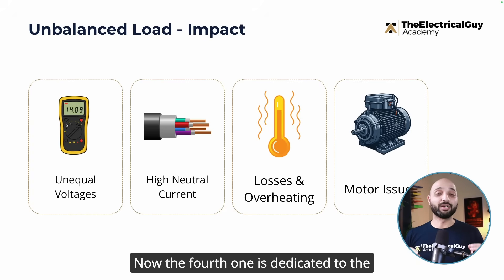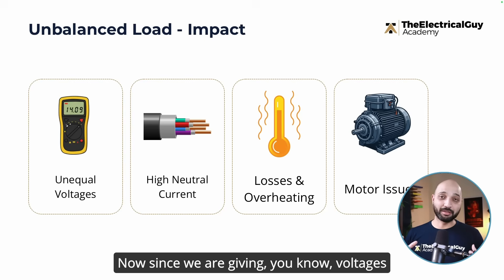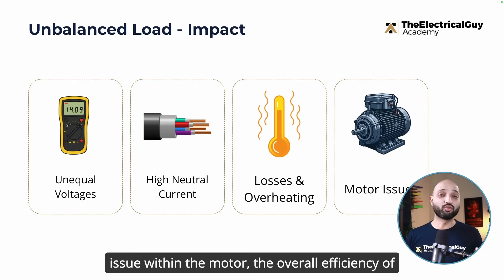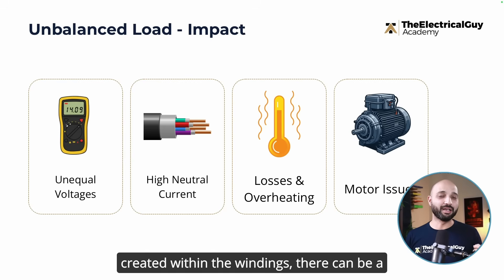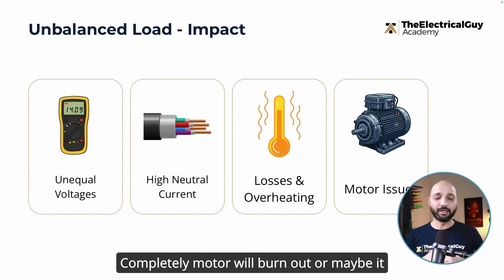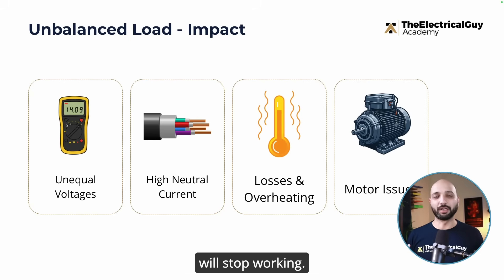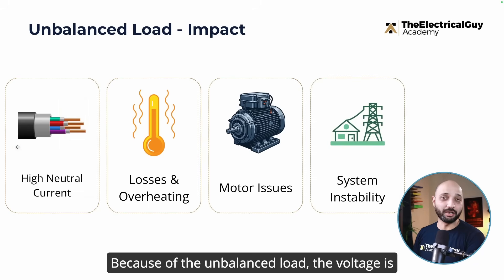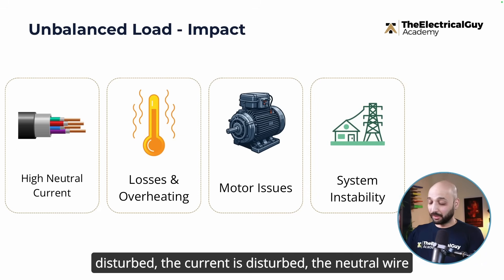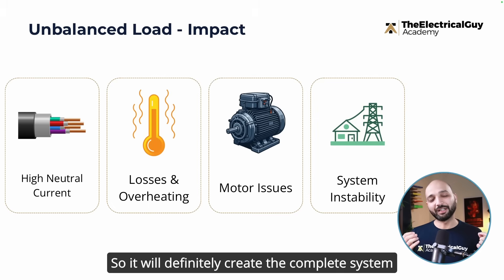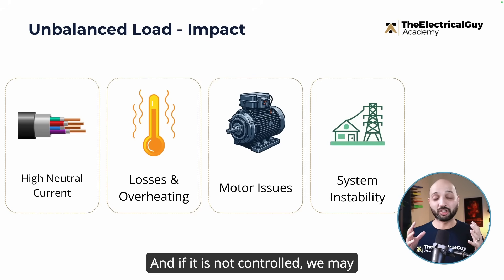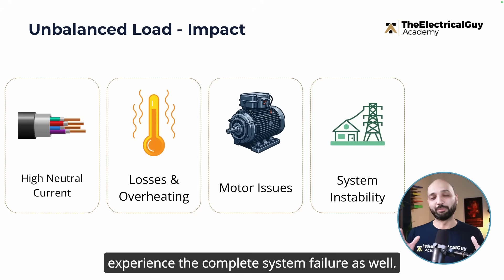The third impact is losses and overheating: increasing current raises I²R losses, and if these reach a certain limit overheating begins, leading to insulation breakdown, short circuit, and fire — a chain reaction. The fourth impact applies to motors: unequal voltages reduce motor efficiency, cause vibrations due to unequal magnetic fields in the windings, and can lead to premature motor failure or complete burnout. The fifth impact is system instability — voltage, current, and neutral are all disturbed, which can lead to complete system failure if not controlled.